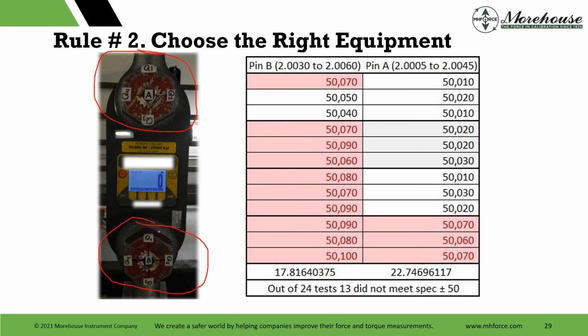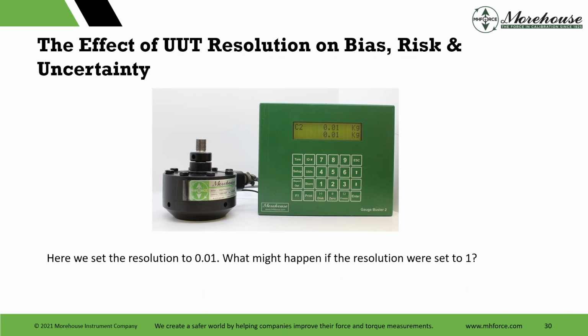And as we turn that pin, and the pins are pretty similar, as we turned it and took measurements, 20 out of 24 tests did not meet the spec of plus or minus 50 pounds. Now, if that manufacturer were to spec this device with that pin at 0.2%, plus or minus 100 pounds, there's only one test that is right on the line. Everything else would be in. So draw your own conclusions.